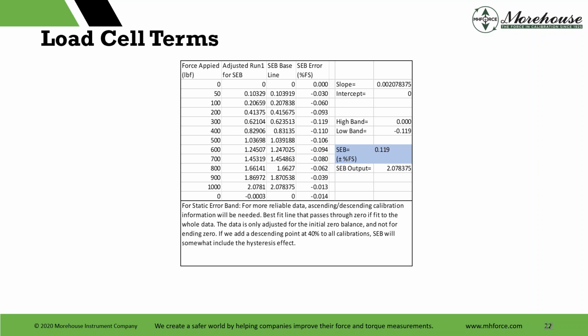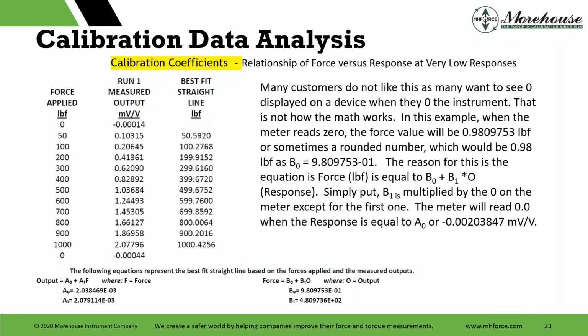And as said here, we're going to fit it, we're going to look at it, we're going to plot the SEB baseline exactly like we were doing for nonlinearity, and then we're going to subtract the two. And in this case, the SEB was 0.119%. So that is there. Fairly easy math to do in Excel. SEB is a little bit harder, while nonlinearity is really easy. Hysteresis is very easy as well. Then we're looking at coefficients. It's something else we put on our certificates, and before we get to hysteresis.